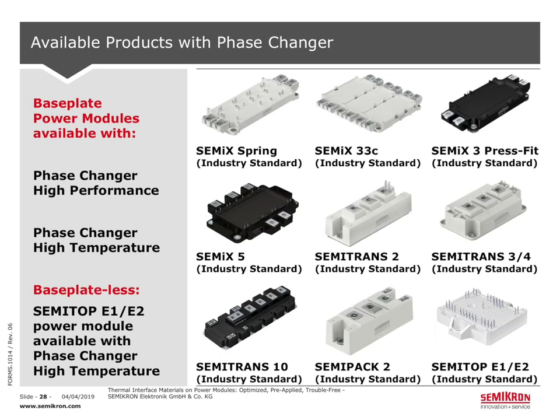The disadvantage here is the performance. If you compare the phase changer against our standard thermal paste that we use as a design standard or reference, then we have a 10% reduced RTH. If we compare the HPTP, the high performance thermal paste, to the standard on that module, then we have a 40% reduced RTH, thermal resistance. That means if you want the easiest handling, again, you go with a phase changer. If you want the highest performance, you should use the high performance thermal paste.